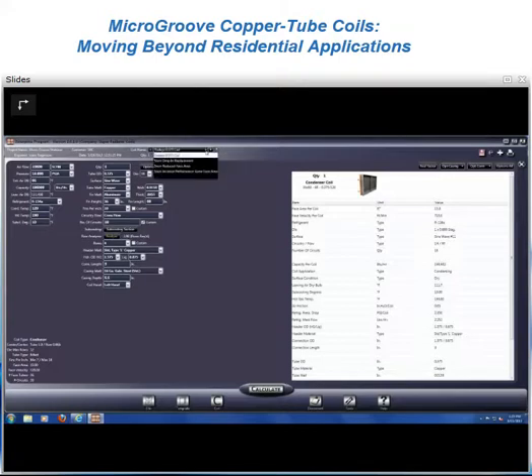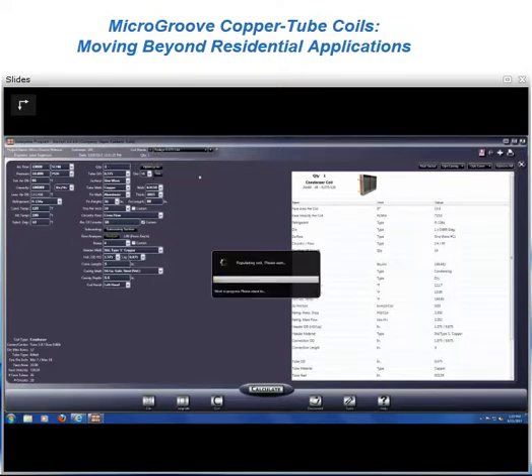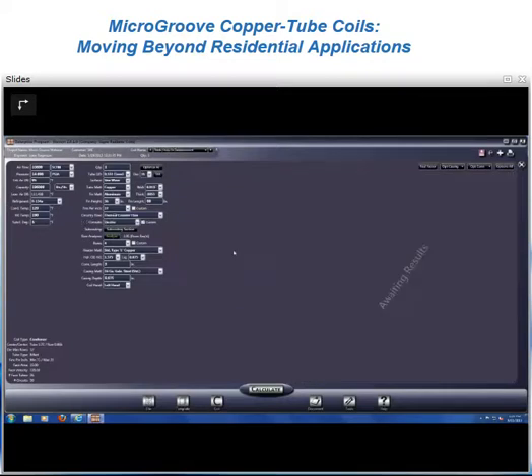So the first step we want to look at is, let's take this coil, change nothing physically about the footprint of the coil, and put a 5mm coil in there. So I'll switch over to one I've preloaded for a 5mm replacement of this. So our inputs for the air side and refrigerant are the same. Change it now to the 5mm, which as Matt said is what we call number 26.